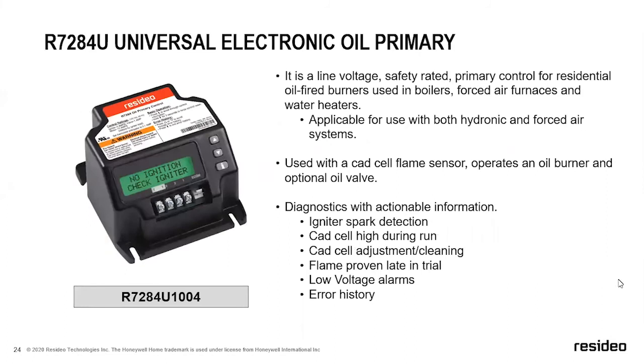So far, we've talked about controls for gas, heat pumps, and hydronics. And now we're going to move on and talk about our R7284U, which is a universal electronic oil primary. So this product here is for the oil market. It's a line voltage safety rated primary control, and it's going to be utilized for residential oil-fired burners used in either boilers, forced air furnaces, and water heaters. So this device can be either used in hydronic or forced air systems.